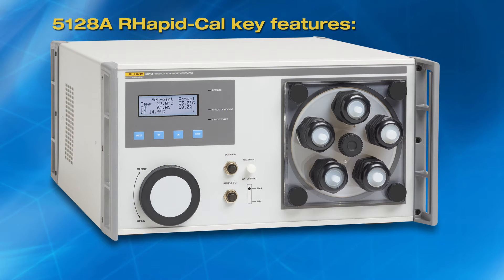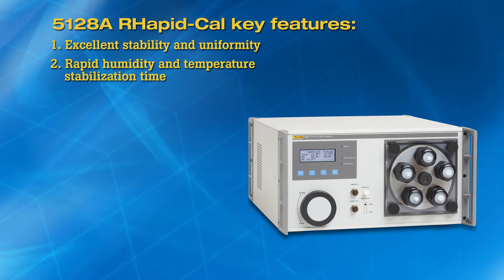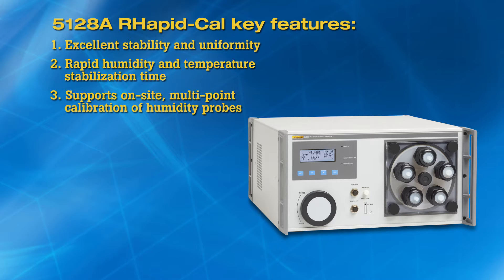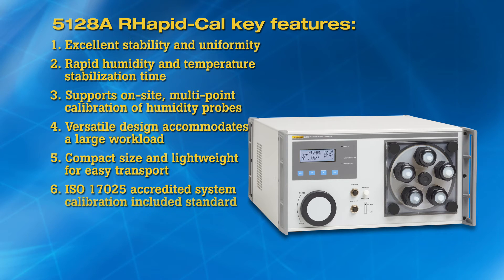There are seven key features that distinguish the 5128A RHapid-Cal. One, excellent stability and uniformity for accurate, dependable humidity probe calibration. Two, rapid humidity and temperature stabilization time for high calibration throughput. Three, supports on-site multi-point calibration of humidity probes. Four, versatile design accommodates a large workload. Five, compact size and lightweight for easy transport. Six, ISO 17025 accredited system calibration included standard. Seven, easy to maintain.